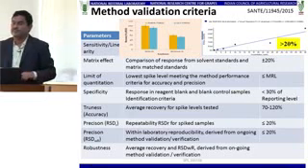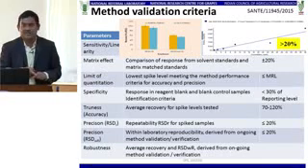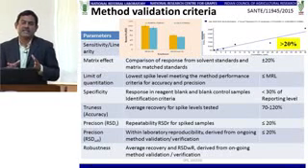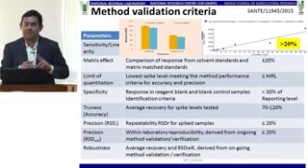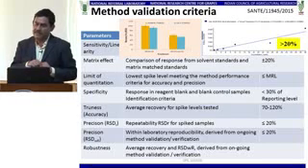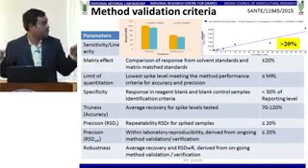So this is very important. Otherwise, you need to probably recheck the linearity. So in linearity, there are certain things. If you study this Sante guideline, first you redo the calibration, and if the problem still persists, then you try to squeeze into a shorter dynamic range instead of going to such a high level.